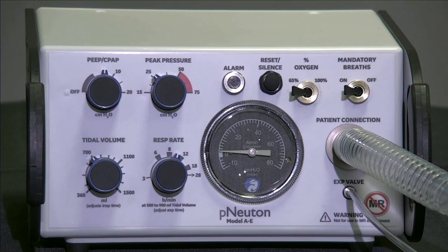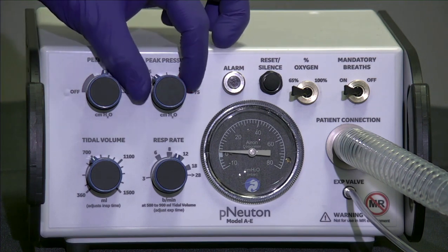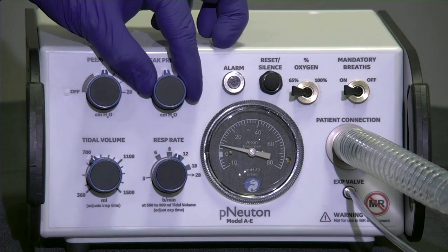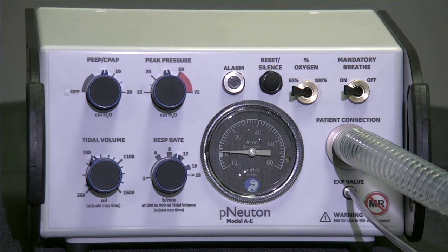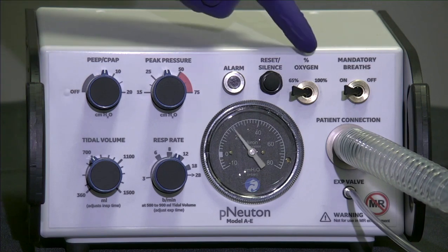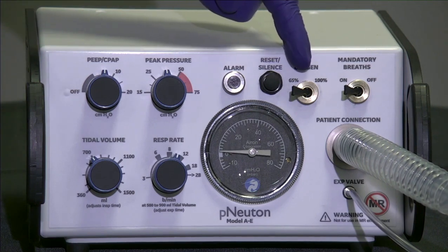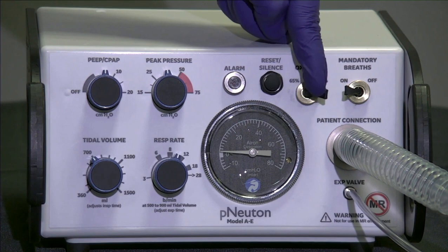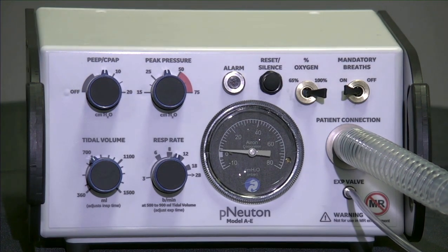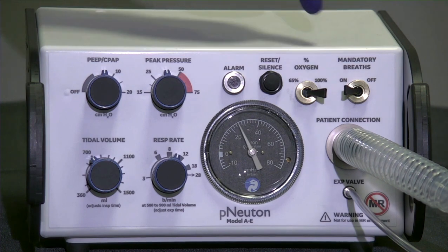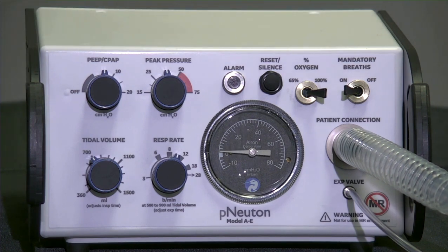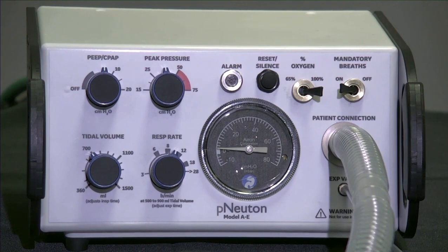The peak pressure control should be set above the delivered pressure at a desired setting to assure patient safety. Set the percent O2 control at either 65 or 100% so the ventilator is ready for any critical situation. Make sure your mandatory breath is set to on. Add PEEP as needed. The pNeuton A-E offers other modes of operation including CPAP and pressure limit.